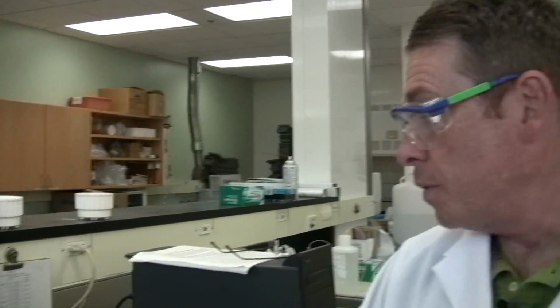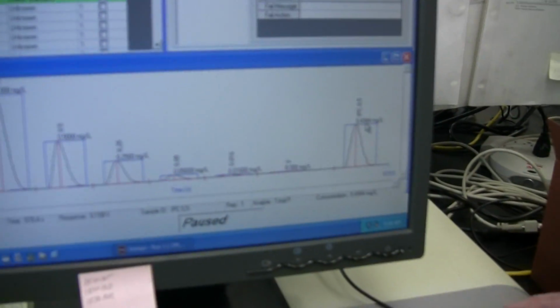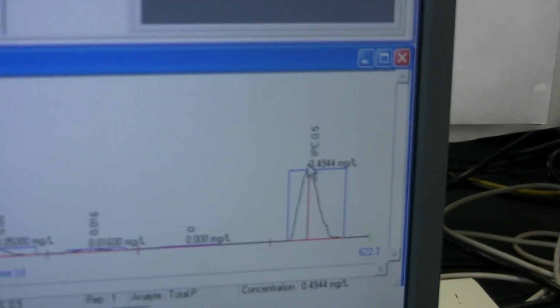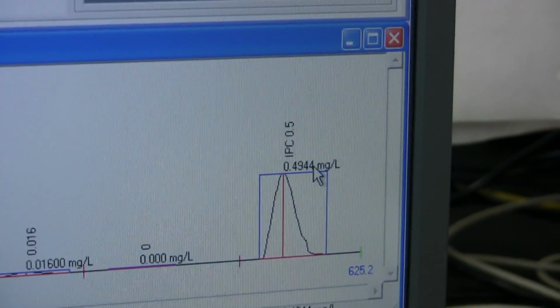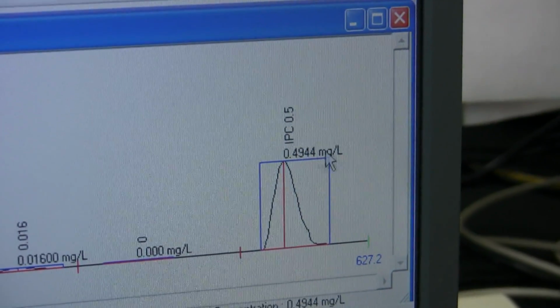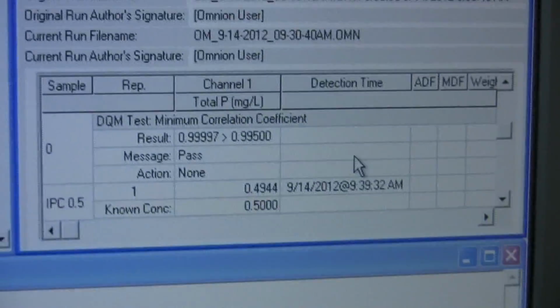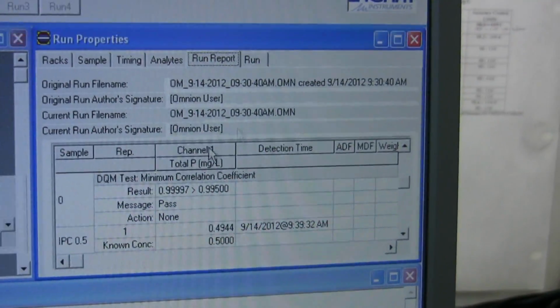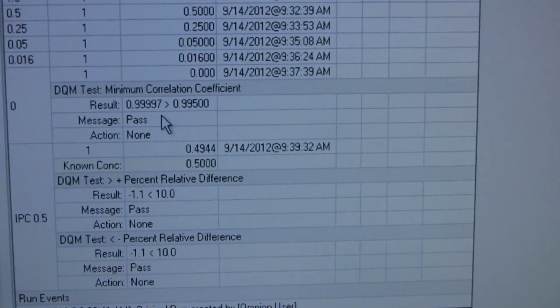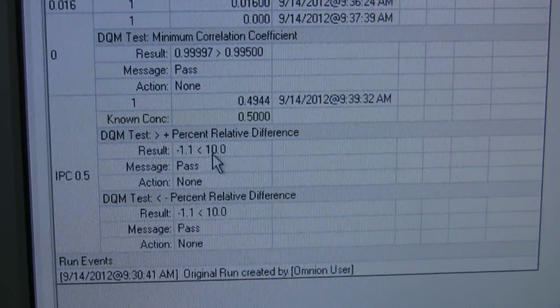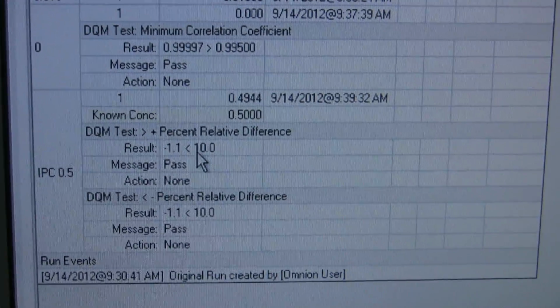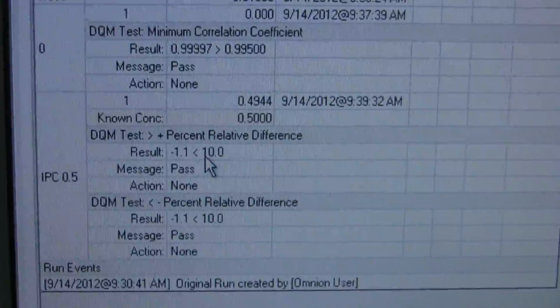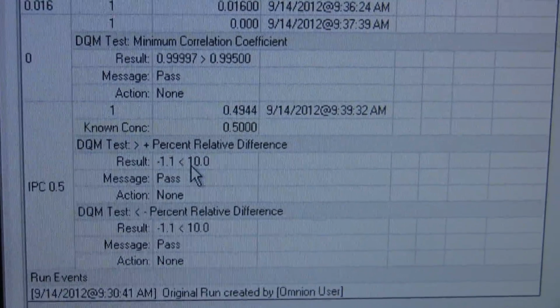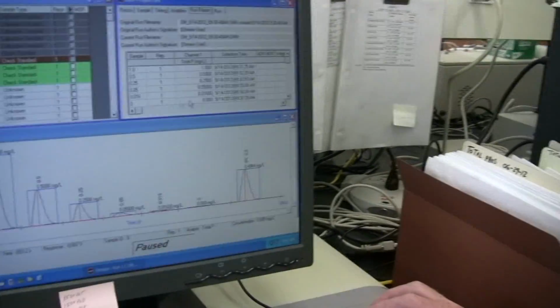So in most of our quality control, it's plus or minus 10%. This standard is supposed to be 0.50. It's 0.4944, so it's well within 10% of its value. The instrument is also set up to automatically grade these, so it says that it's within 10% of its true value, so it keeps running. If it were not, the instruments are nice in that they're automated. It will stop and throw up a window and say, this failed. What do you want to do? Do you want to keep running? Do you want to do something? So these instruments are nice in that sense.